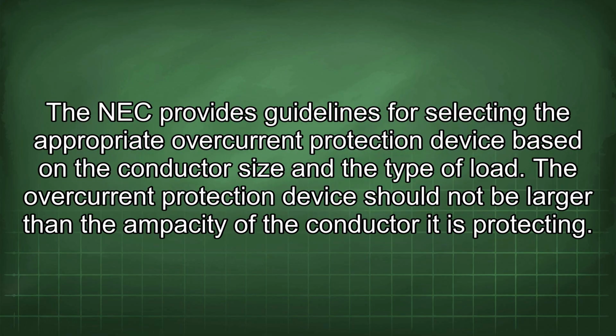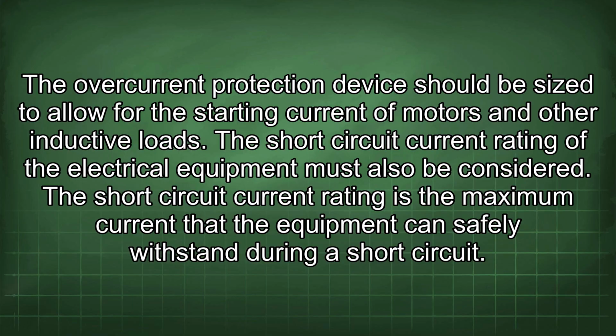The NEC provides guidelines for selecting the appropriate overcurrent protection device based on the conductor size and the type of load. The overcurrent protection device should not be larger than the ampacity of the conductor it is protecting. The overcurrent protection device should be sized to allow for the starting current of motors and other inductive loads.